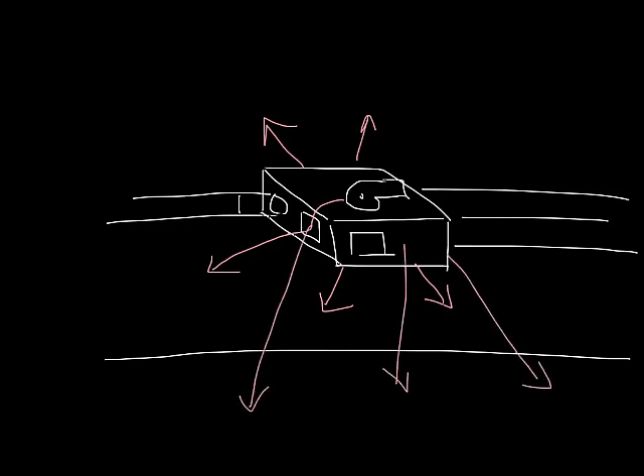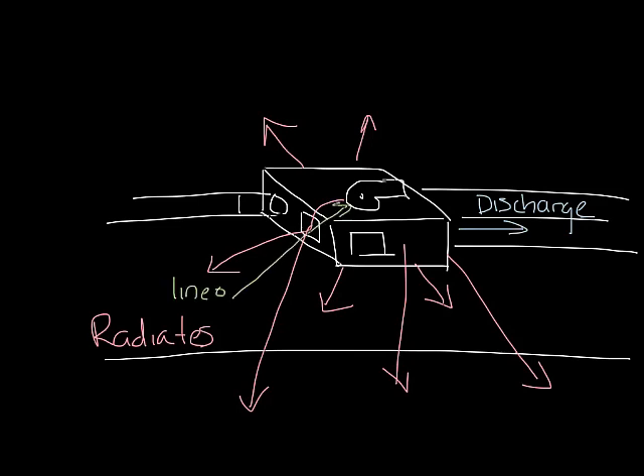So fan boxes have a motor-blower combination, which creates sound in the box. This sound can travel out the induced air inlet and into the ceiling plenum. Then the radiated sound can pass through the ceiling plenum into the space. The discharge sound comes out of the box, through the ductwork, and then into the space. Part of the challenge is that you have line of sight to the motor. You can actually look in the induced air inlet and often see the motor-blower combination.